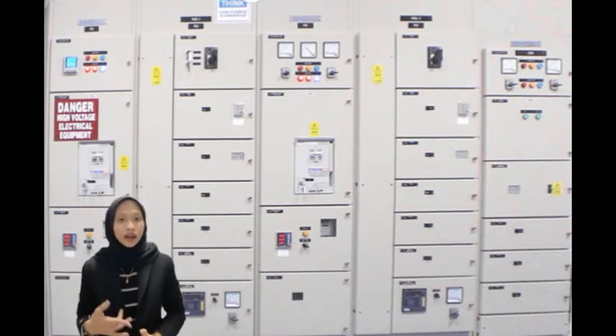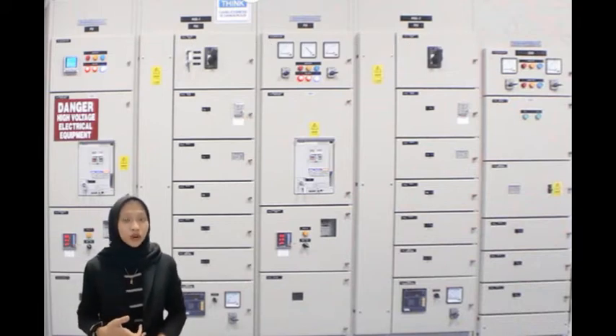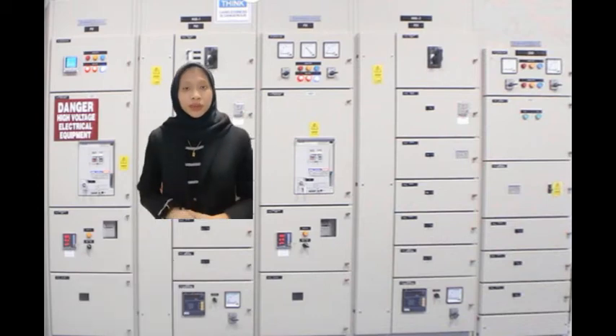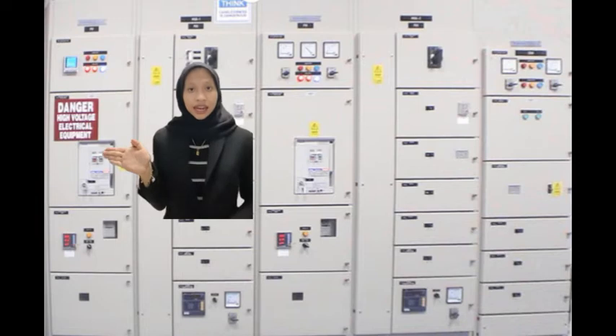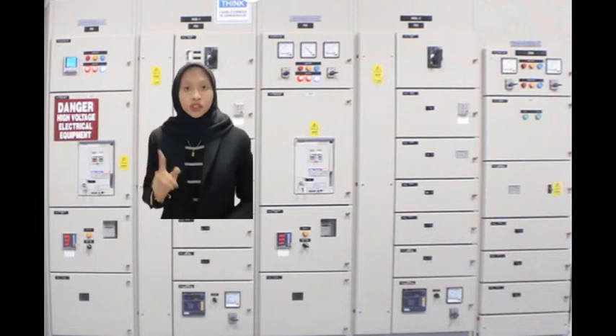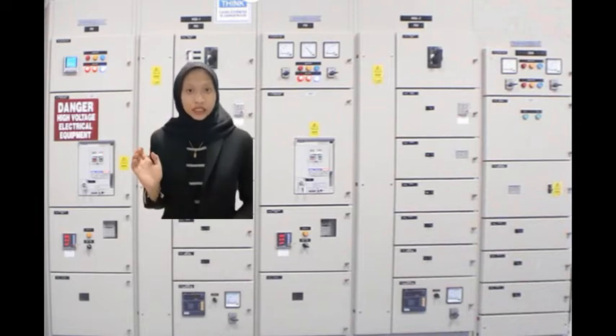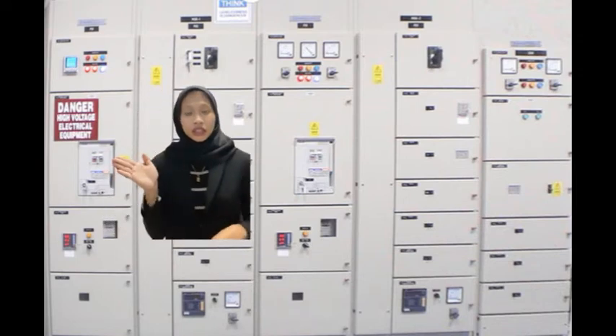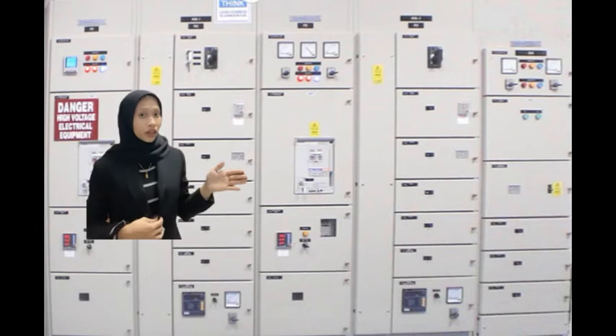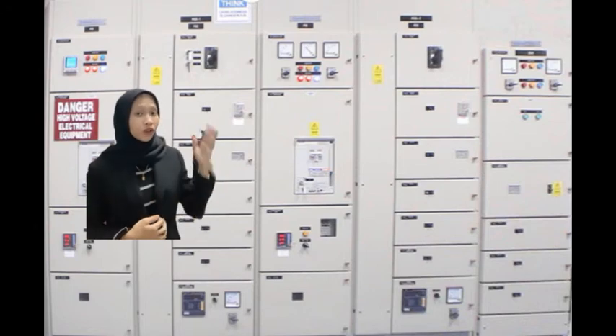I will explain about busbar coupling of MSB1 and MSB2. Usually we do the busbar coupling for fault or maintenance purposes. If we want to do maintenance at the ACB at MSB1, we must turn off the ACB first. Before we turn off the ACB, we must turn off all the loads. We must get permission before turning off the loads.